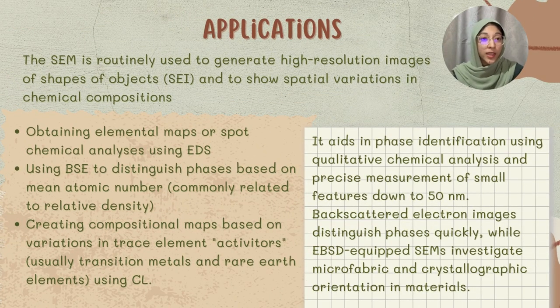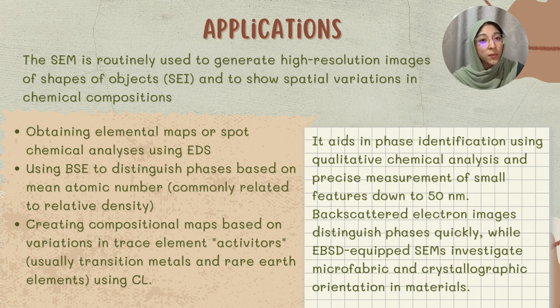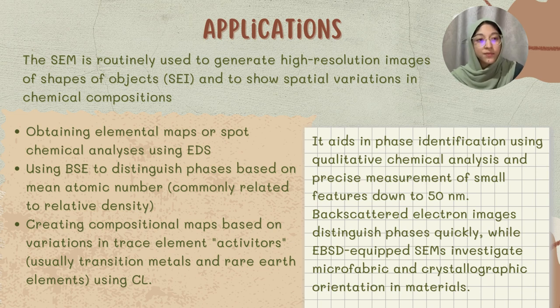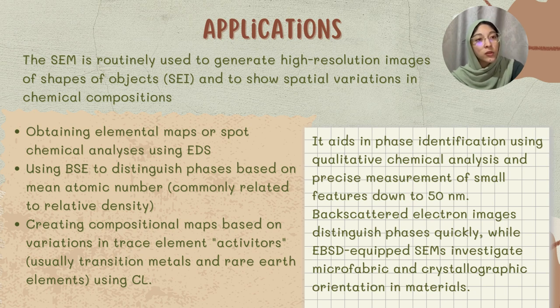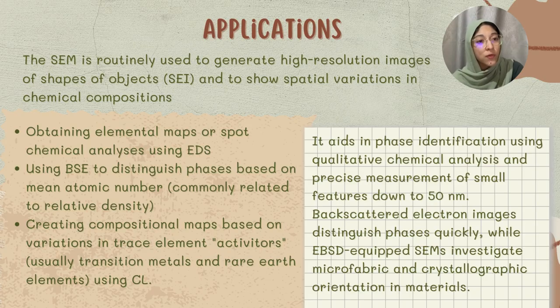Applications of the scanning electron microscope: SEM is used to obtain elemental maps or spot chemical analyses using EDS, and uses backscattered electrons to distinguish phases based on mean atomic number. SEM also creates compositional maps based on variation in trace element activators, and aids in phase identification using qualitative chemical analysis and precise measurement of small features down to 50 nanometers.